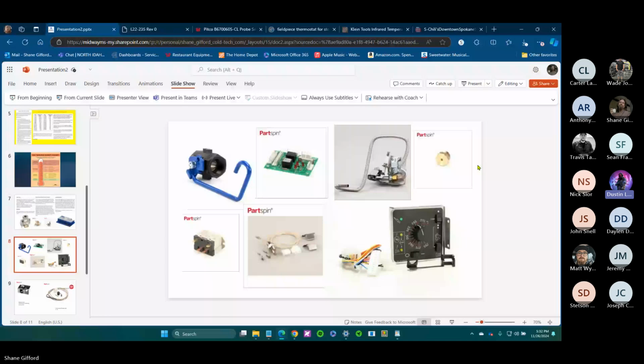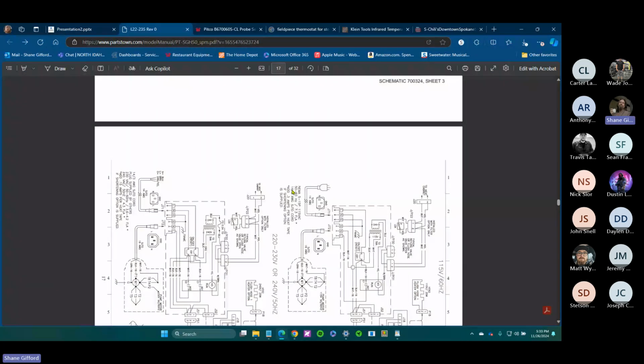So quick question, because I don't know the answer: how do you know if you have the right one? Yep. So if you look at, I keep calling it a spud, it's an orifice, there will be a number stamped into it, and it should also say LP or NG for liquid propane or natural gas. Another thing is, I believe the natural gas hole, the little orifice hole, is larger than liquid propane. LP, you're going to have a much smaller hole. But those are just a couple of things to look at. And if all else fails, you can always pull up the information for the unit.